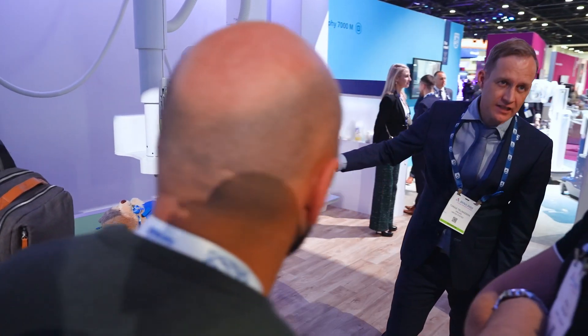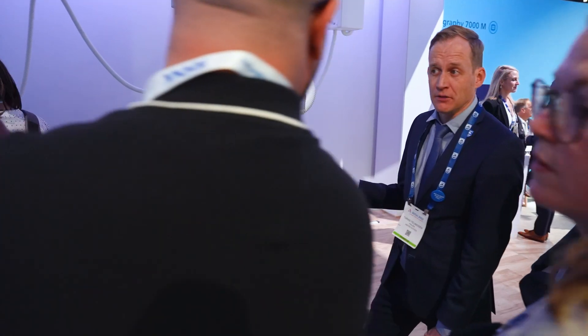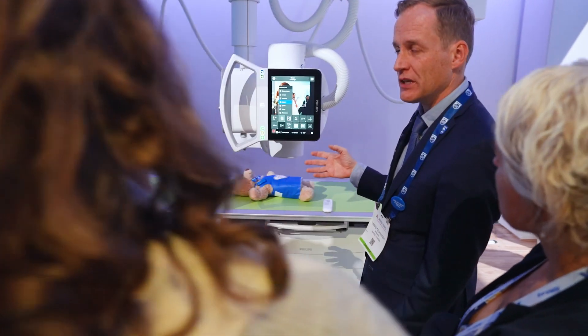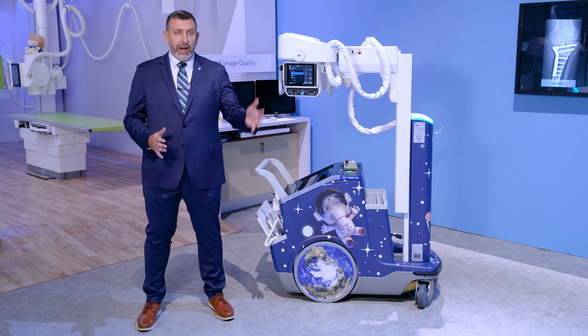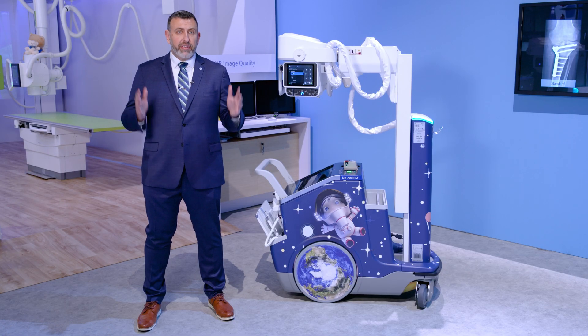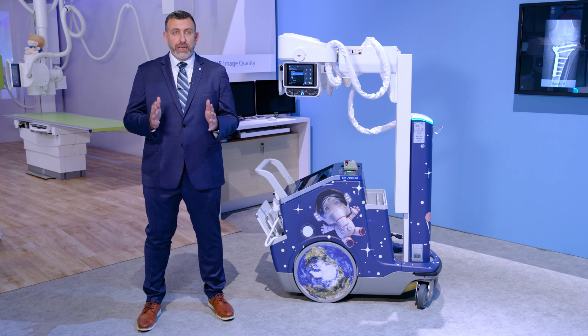On the DR7300C, the advanced workflow is really resonating to save time as staff is slammed with more patients than ever. We introduced a new function called Smart Collimation Thorax, which saves up to 35 seconds per chest x-ray by automating the vertical height of the wall stand and the collimation of the patient, so it's always collimated correctly at the correct height.